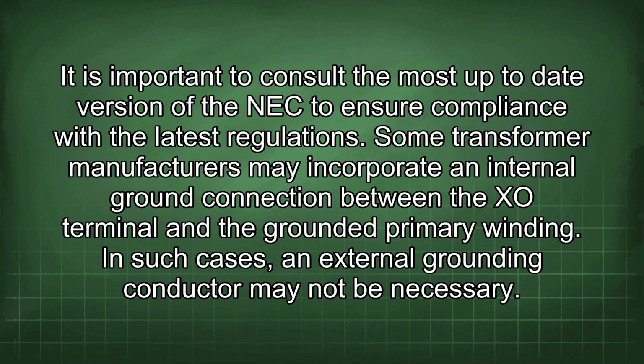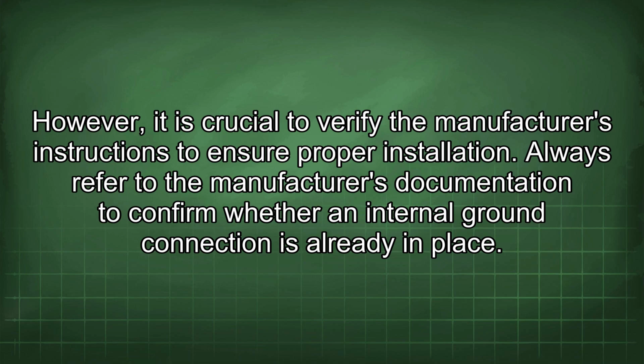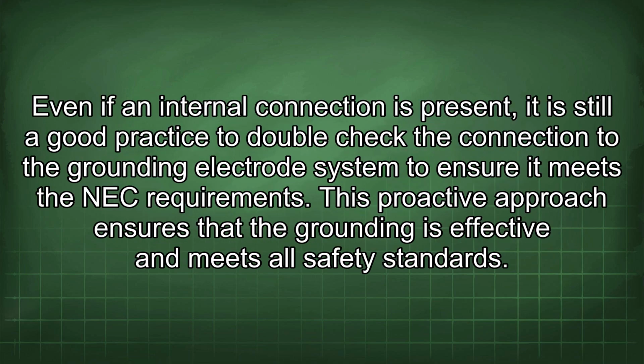Some transformer manufacturers may incorporate an internal ground connection between the X0 terminal and the grounded primary winding. In such cases, an external grounding conductor may not be necessary. However, it is crucial to verify the manufacturer's instructions to ensure proper installation. Always refer to the manufacturer's documentation to confirm whether an internal ground connection is already in place. Even if an internal connection is present, it is still a good practice to double-check the connection to the grounding electrode system to ensure it meets the NEC requirements. This proactive approach ensures that the grounding is effective and meets all safety standards.